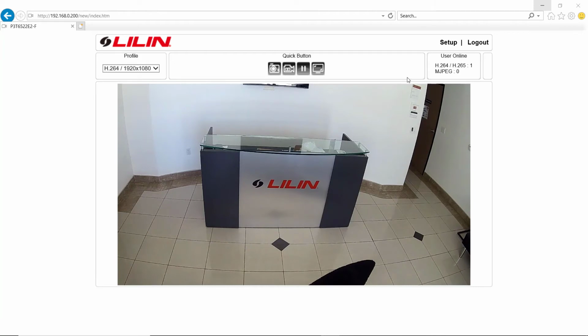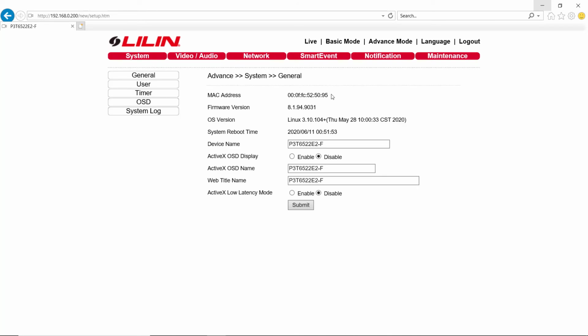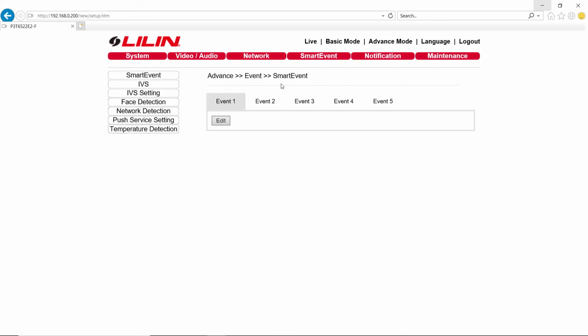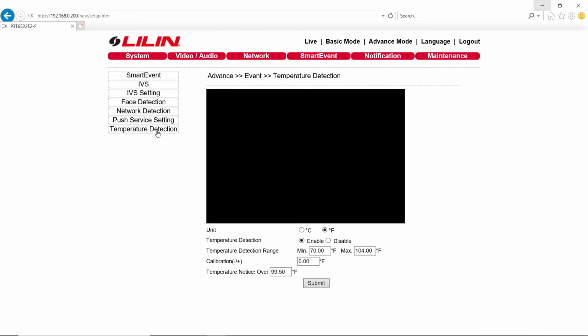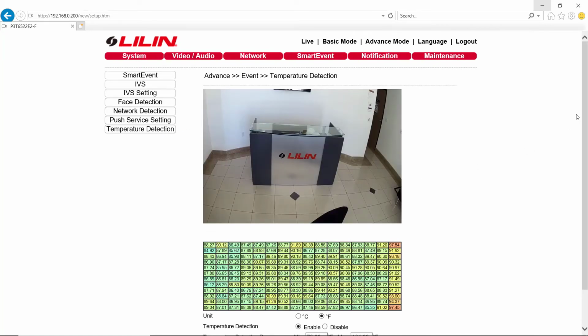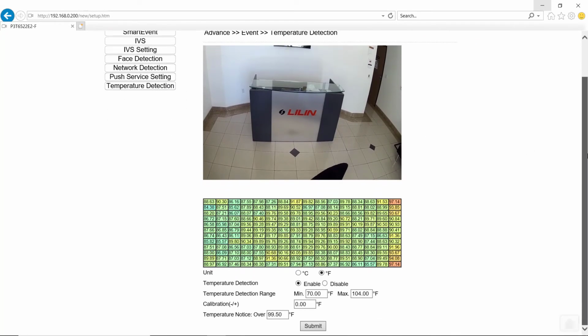So again, we log into the camera's web interface. We click on the Setup button up in the upper right-hand corner. And then toward the upper middle, there's a button called Smart Event. We click here, and then at the bottom left, we click Temperature Detection. And you'll notice that near the bottom, there's actually a grid of 12 by 16 pixels showing different temperature readings. That's actually the readings coming off of the thermopile sensor in the camera, which is then overlaid to the image. This is how we get temperature readings from different sectors of the image when we're actually reading temperatures.